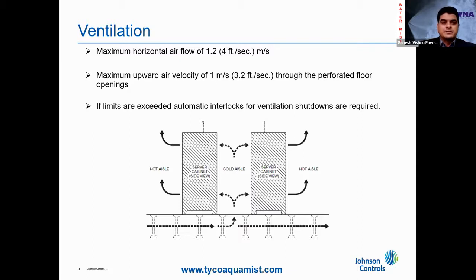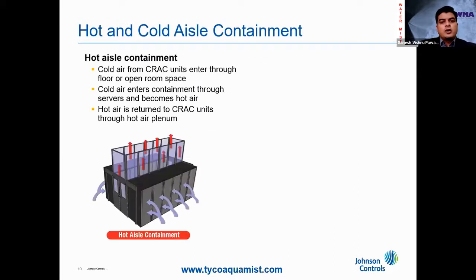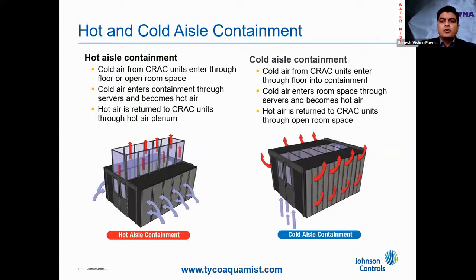Another important aspect while designing is the hot and cold aisle containment. In hot aisle containment, the cold air from the CRAC units enters through the floor or an open room space. This cold air passes through the servers and becomes hot air, which is returned back to the CRAC units through the hot air plenum. Whereas in cold aisle containment, the cold air from the CRAC units enters through the floor into the containments. This cold air enters the room space through the servers and becomes hot air.